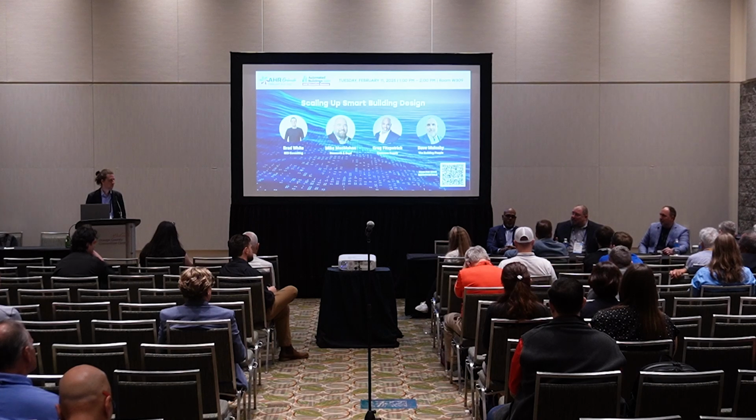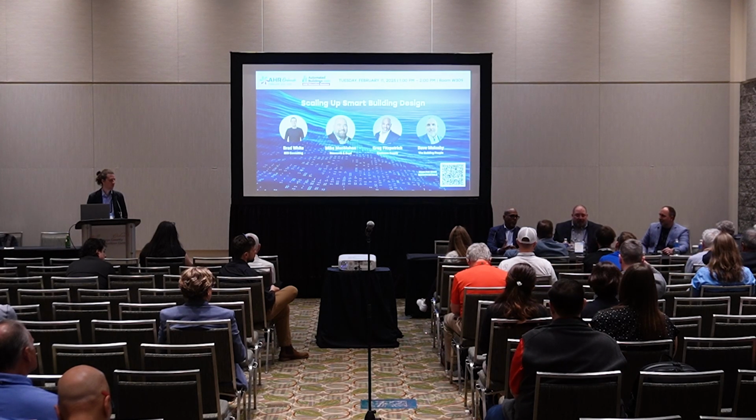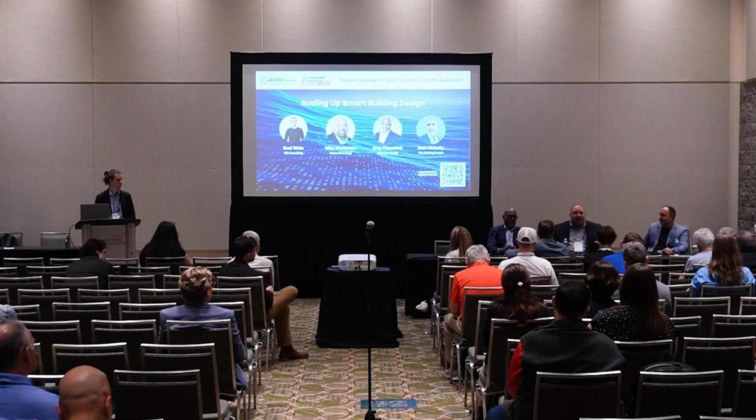One of the stories they were telling me was we got so smart we became dumb and we tripped on ourselves. So they brought all of their health system assets together, and somebody made a change in Niagara, and they didn't realize it affected all of the hospitals. So instead of just shutting down the BMS at the one hospital, they kind of knocked them all offline because they didn't realize the power that they had at their fingertips, because the person making the change had the wrong privilege levels. He goes, so we learned that, and then we learned this.